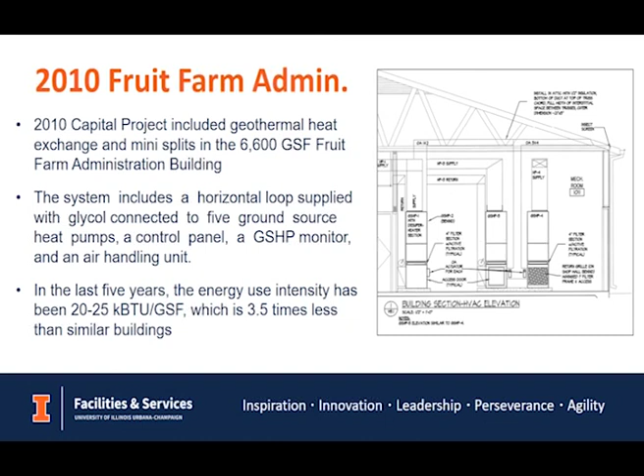The first one started in 2010, the fruit farm admin building. That was a capital project, 6,600 gross square feet, energy upgrade. The system included a horizontal loop supplied with glycol connected to 5 ground source heat pumps. In the last 5 years only, the energy use intensity has been between 20 to 25 kBTU per square foot, which is 3.5 times less than similar buildings.